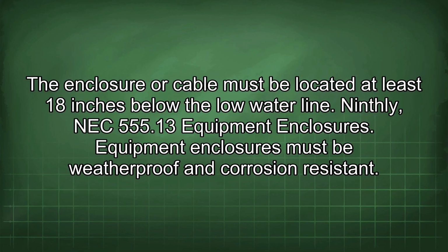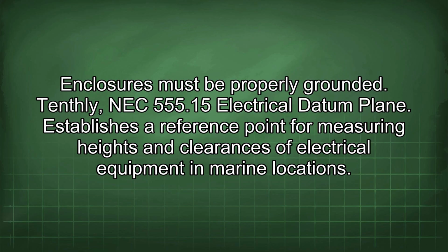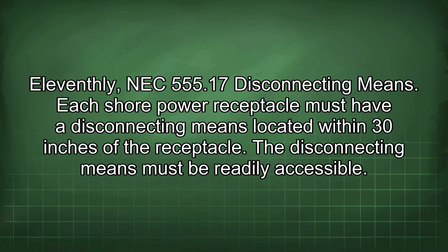Ninthly, NEC 555.13 equipment enclosures. Equipment enclosures must be weatherproof and corrosion resistant. Enclosures must be properly grounded. Tenthly, NEC 555.15 electrical datum plane. Establishes a reference point for measuring heights and clearances of electrical equipment in marine locations. 11thly, NEC 555.17 disconnecting means. Each shore power receptacle must have a disconnecting means located within 30 inches of the receptacle. The disconnecting means must be readily accessible.